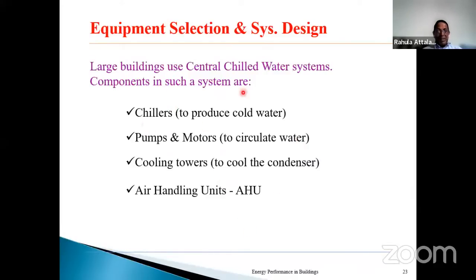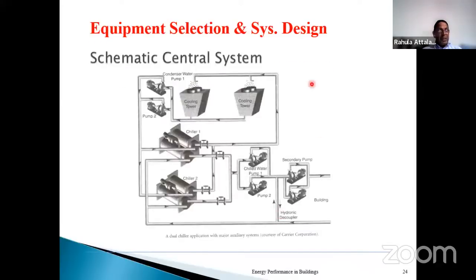The large building with a central system will have components. The heart of the cooling system is the chiller, which will produce the cold water. So cold water will carry the coldness to the end use level, or it will transfer into air, and air will carry the coldness to the end use. That's possible. That's all air systems. Then you will need pumps and motors to circulate the water and drive the pumps. We'll have cooling towers to cool the condenser for heat rejection, and air handling units to carry the coldness from the chiller directly or through a secondary circuit. So this is a typical central system. Generally you have different design strategies. So this all comes under the design, equipment selection, and system design.